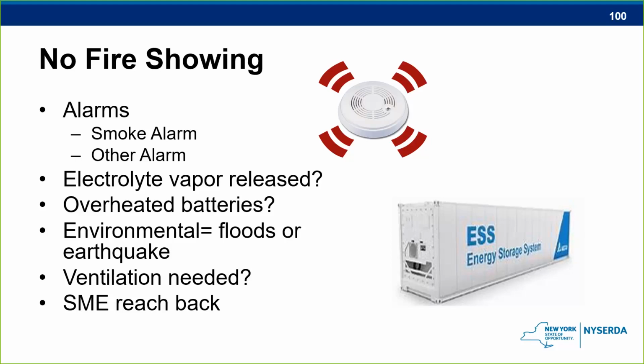And also, the fire department would like to have a subject matter expert, so someone that they can call and say, hey, listen, I'm at this location. What type of chemistry is in there? What do you have for a suppression system? Are you showing anything on that BMS? Now we get into this thing called the BMS that Jennifer also mentioned. That was a component of it, the eyes and ears, she called it, the brains of it. Does that show any type of data that we should be concerned about? Is it showing any type of rise in temperature? And if so, are we at a temperature where we possibly could have a vent of those gases into that? Next slide, please.